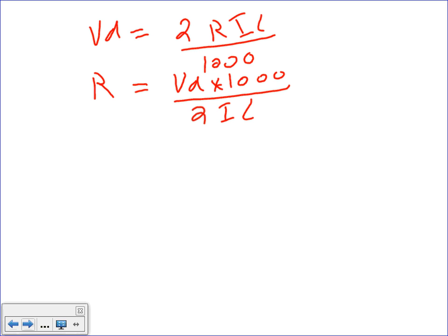Okay. Then equal, so I need to find now, look at what we're going to do. I want to find R, and guess what I do? From R, I can go to table number 8 and size based on R and find the conductor.